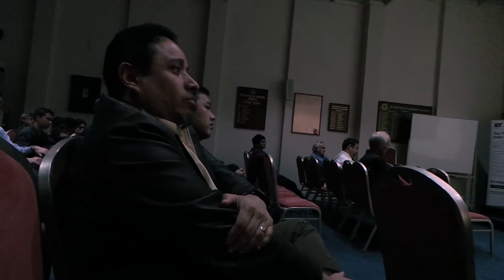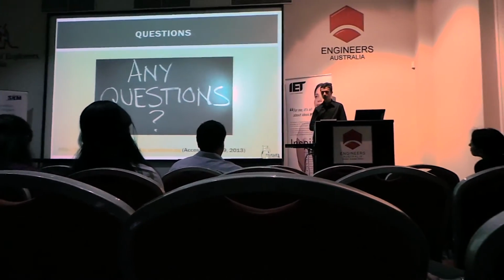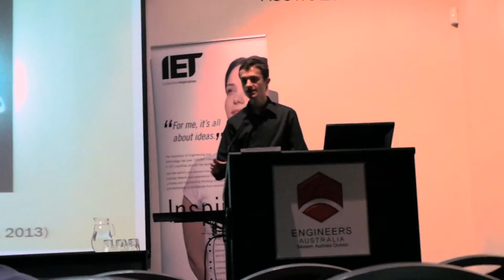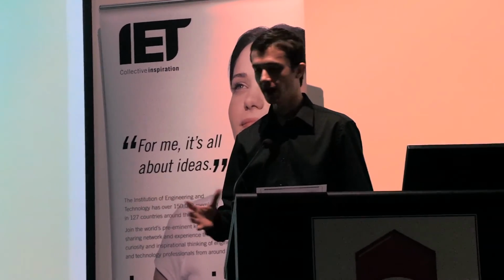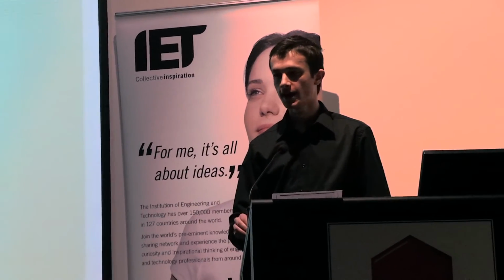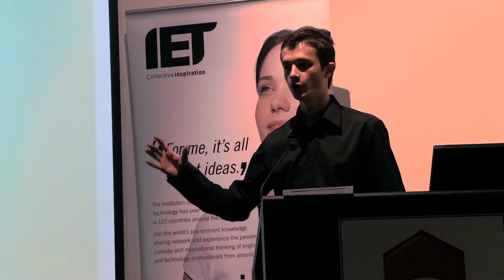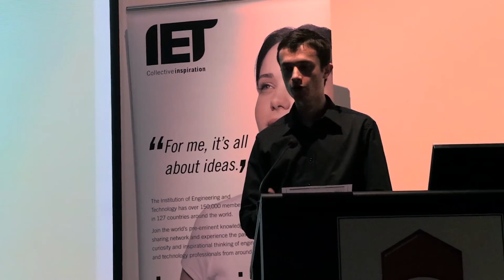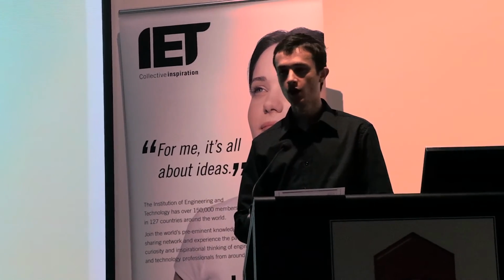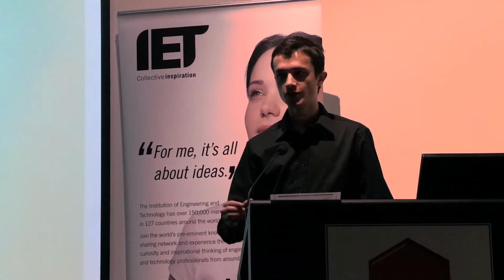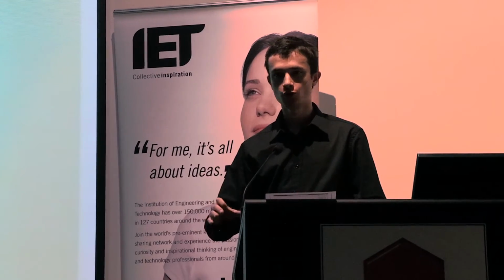How difficult or easy is it to implement this in a real system? You're saying my algorithms will be implemented in Rio Tinto. What is implied in that? What do you need to do to implement your algorithms in Rio Tinto's network? In order to verify the merits of the algorithms, you have to have much more realistic values obtained. What I'm doing here on the Warden-Hale system is assuming very simple parameters, but in order to eventually get it implemented on the Rio Tinto network, I'd have to look at what type of monitoring units I could find that would give me the speeds I want. And in the development of the algorithms, also utilise developed relays by companies such as ABB and see if they can actually integrate with the operational functions of the SPS.